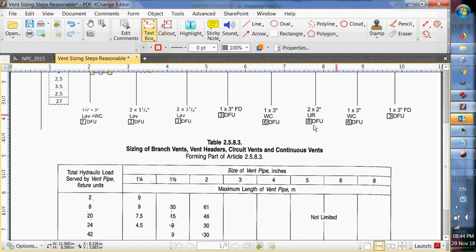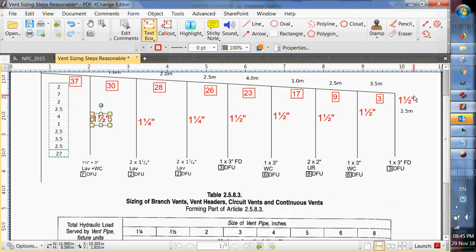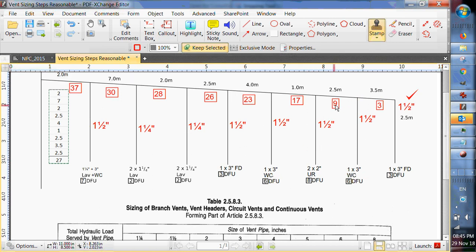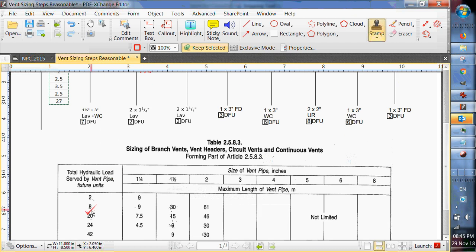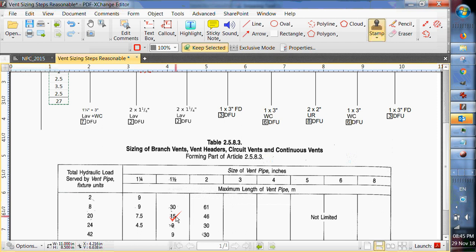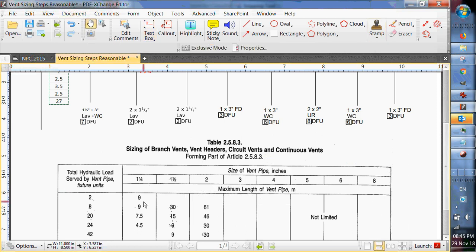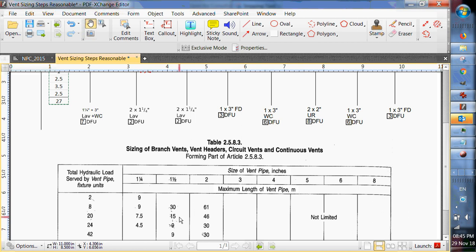So three fixture units that would put us here. Oh, we can go 30 meters with inch and a half, so we're good on that. That one's good. What's the next one? Nine fixture units. Nine fixture units would put us up here. Hmm. Nine fixture units with inch and a half would only give us 15 meters. And we need 27 meters. So we're going to have to pick two inch for this next one.